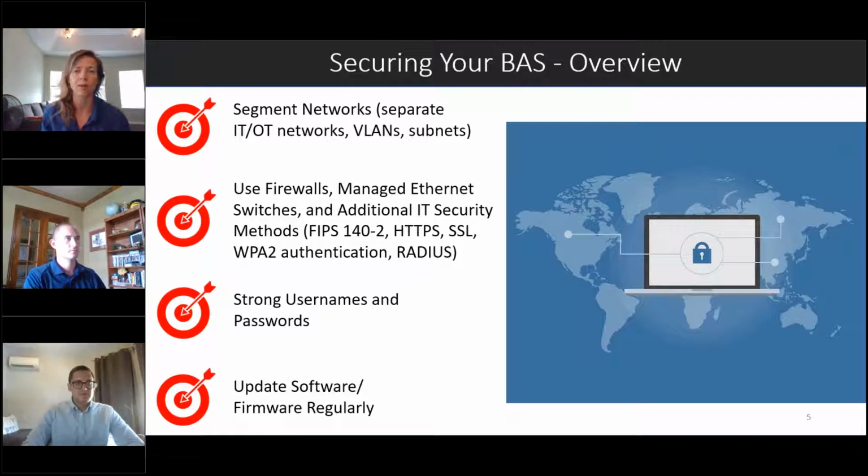And then lastly, if anyone leaves the organization, definitely delete their username. You don't want a disgruntled employee trying to sabotage your building management system, and it's been done before. So just those things are hugely important as well. Yep. And keep in mind, updates to the software and firmware, a lot of those updates do have security features included in them to continue to make the system more secure. So you do want to stay up to date with your software and firmware as cyber attacks continue to change every year. So does the software and firmware to protect against it.